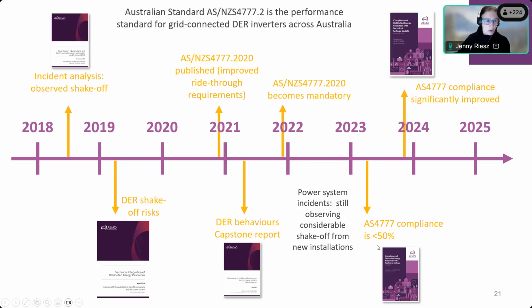The original equipment manufacturers were really critical in supplying to us data around the standards and settings being put onto their devices. We discovered from a whole range of data sets that compliance was less than 50%, and in some cases well less than 50%, of inverters being set properly to that new standard.